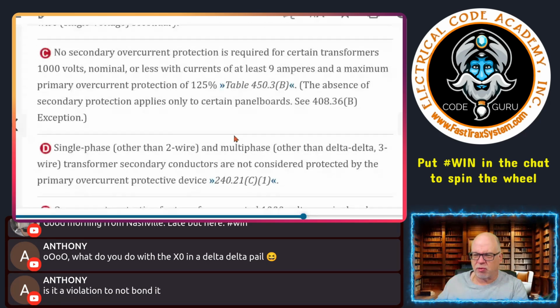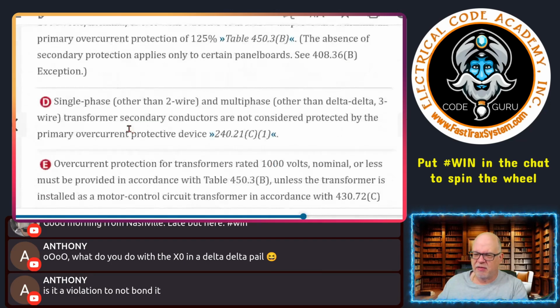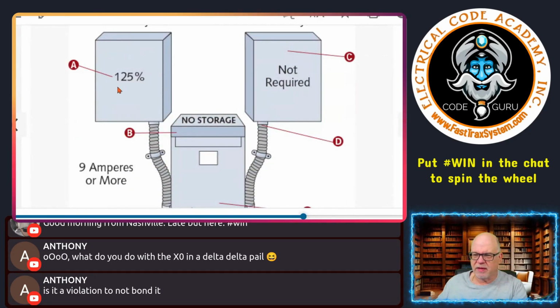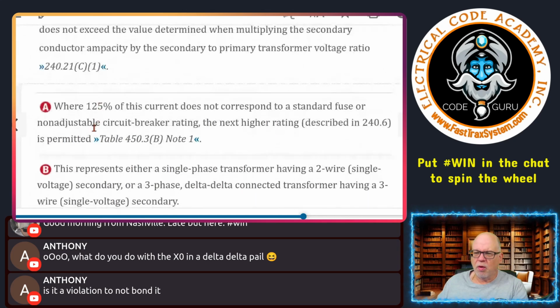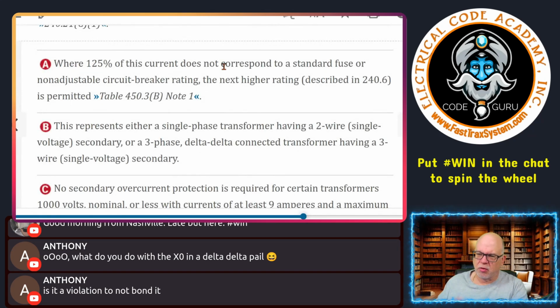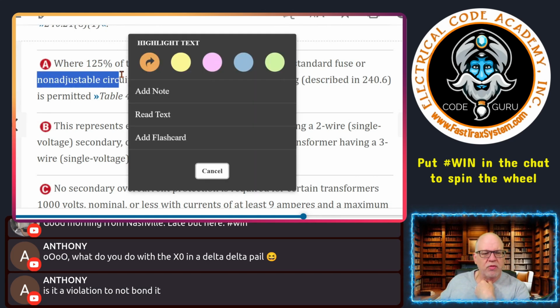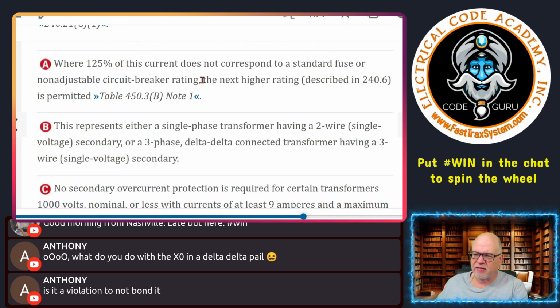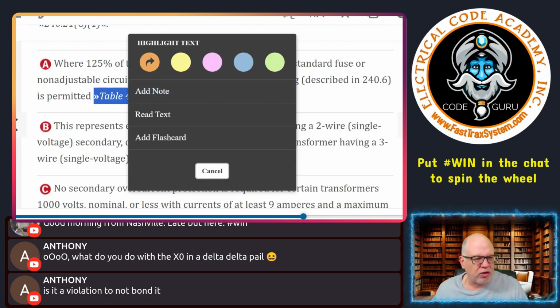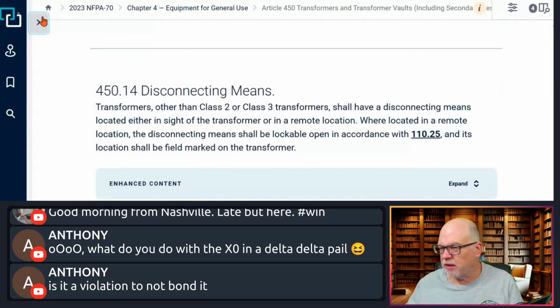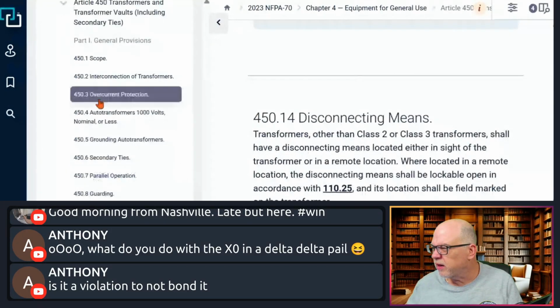All right, let's do some callouts real quick and see what we've got. A seems to be calling out the primary side. A says where 125% of this current does not correspond to a standard fuse or non-adjustable circuit breaker, just a normal circuit breaker, and an inverse time breaker is an example of a non-adjustable circuit breaker, the next higher rating described in 240.6 is permitted. This is all given to us in Table 450.3(B) Note 1. So I want to go look at that table real quick and show you what it's talking about.